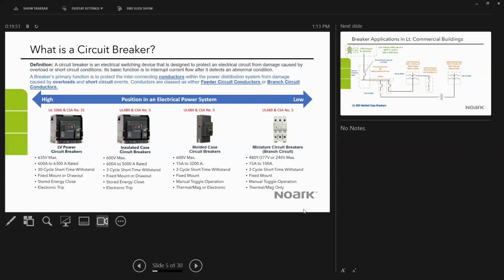In a typical electrical power system, breakers are usually organized in a hierarchy from largest to smallest. So if you think about it in a building or in a machine, you typically have a large circuit protection device or breaker at the main incoming, whether that's the service of a building or the main incoming to a machine. And then as the power flow goes through the system, the breakers get successively smaller.